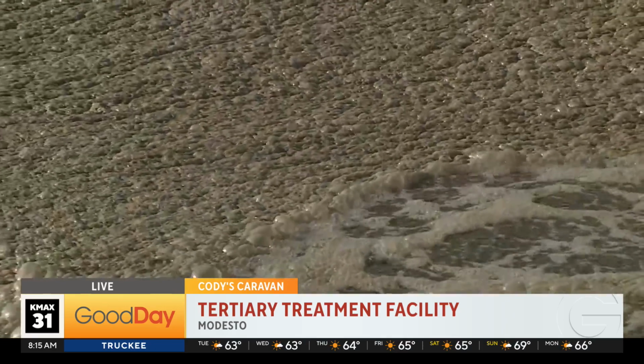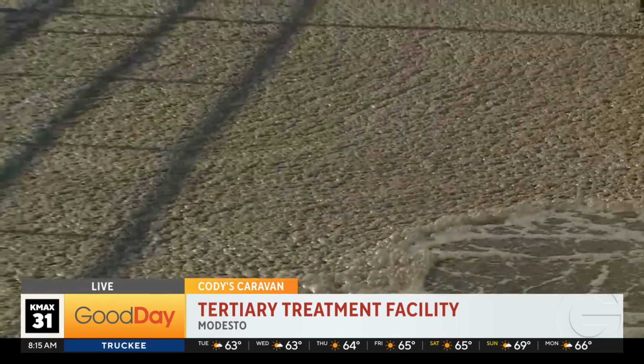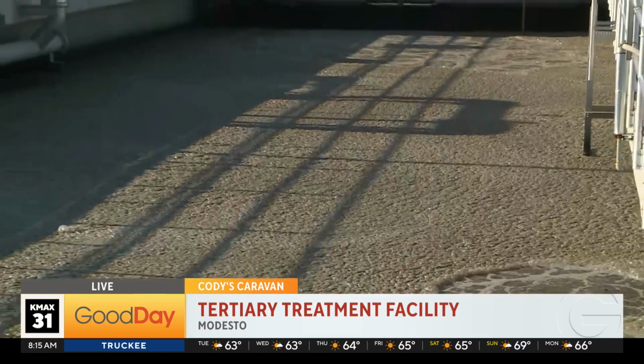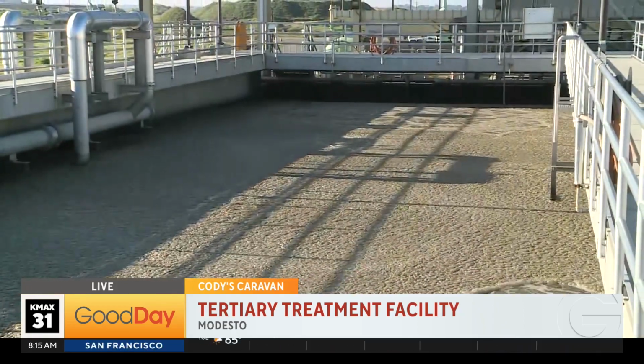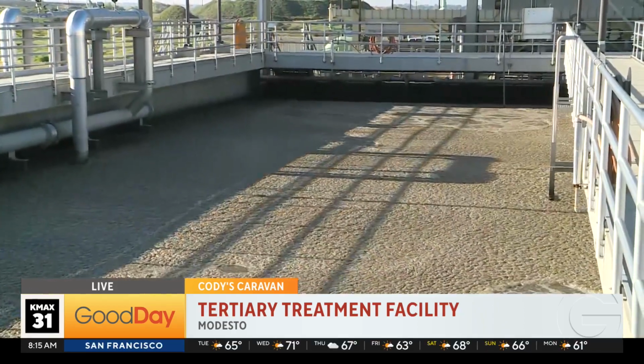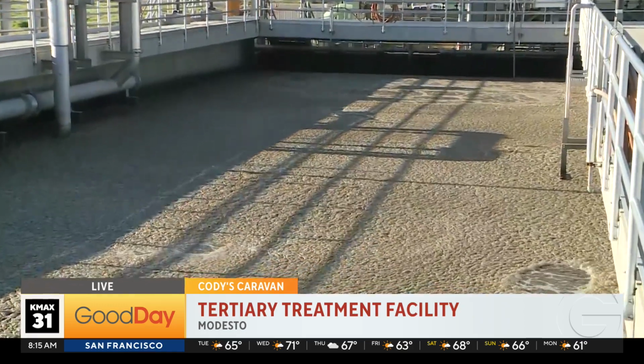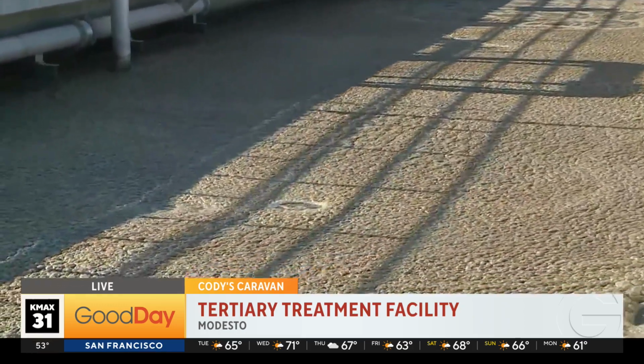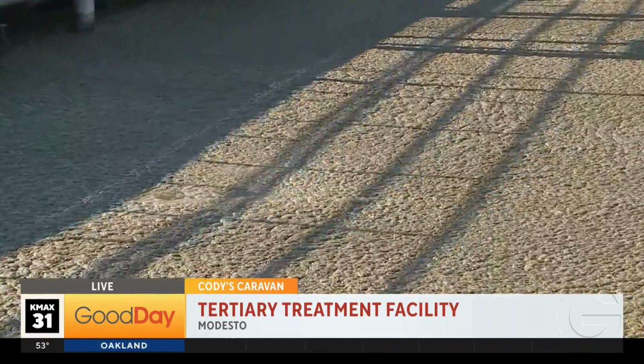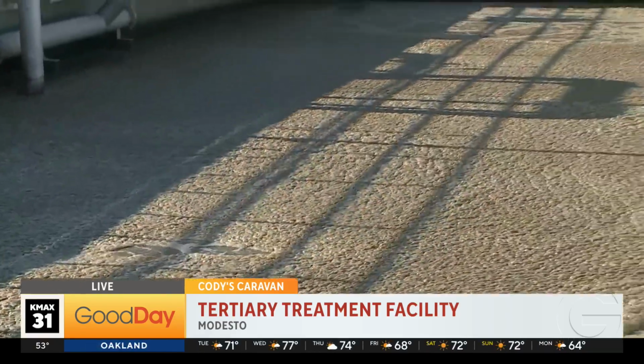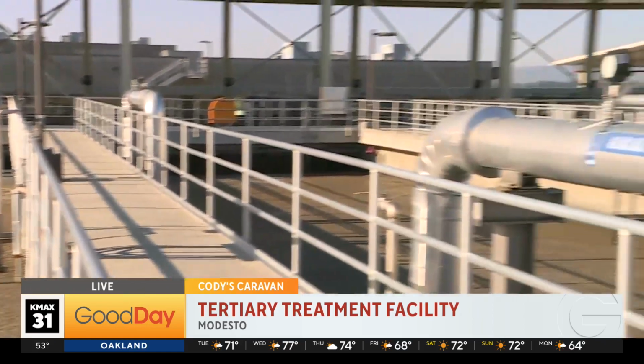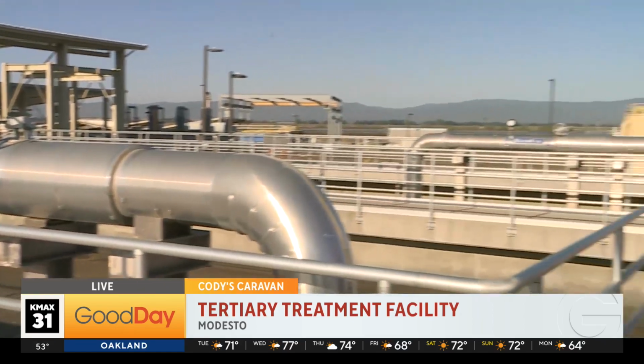Okay. Effectively, what we're trying to eliminate here is ammonia and nitrate. And so in the process of removing ammonia, you convert that into nitrate. So we take that water, recycle it back to the front so we can starve them of a little bit of oxygen, and then they'll change their respiration process to pull the oxygen out of the nitrate, converting that nitrate into nitrogen gas, which diffuses into the atmosphere and just becomes part of the atmosphere. Part of the atmosphere, because the atmosphere is a bunch of nitrogen. Now this water is prepped and ready for filtration.